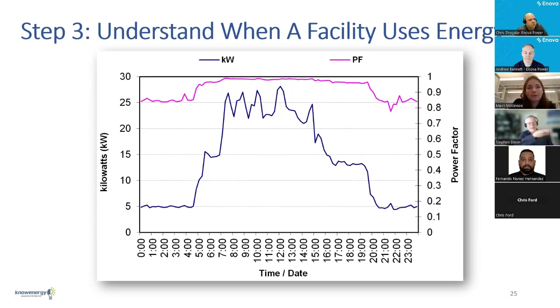This is actually the kilowatts, which is part of how you pay for your electricity, but also the power factor, which is an underlying characteristic of the power you demand from the utility. This can tell me a lot about what a building's doing. I can look at this and tell you that the lights in this building don't go off until 8 o'clock at night, because lights have a higher power factor, so they contribute to this higher reading, and when it drops, that's when the lights are going off.